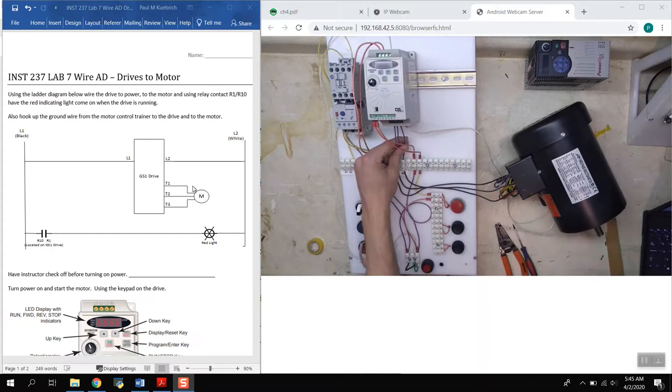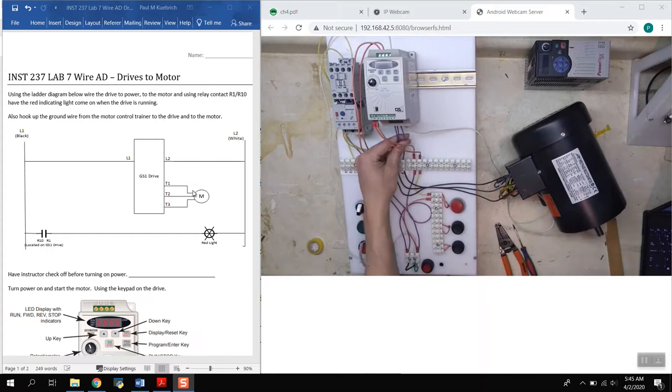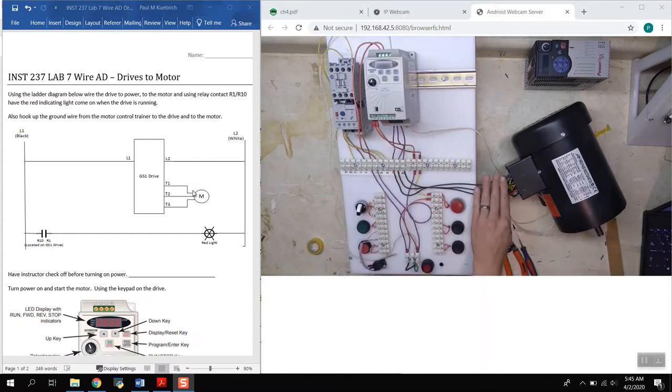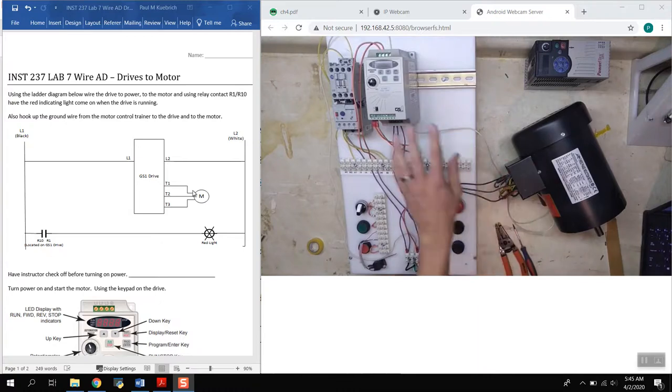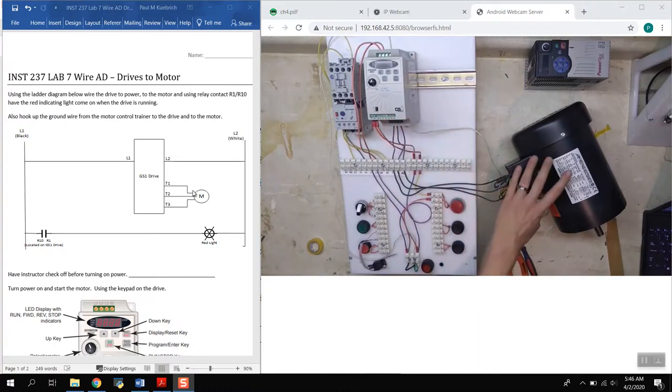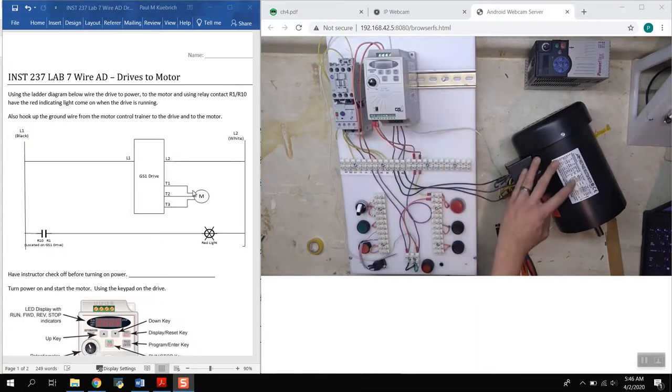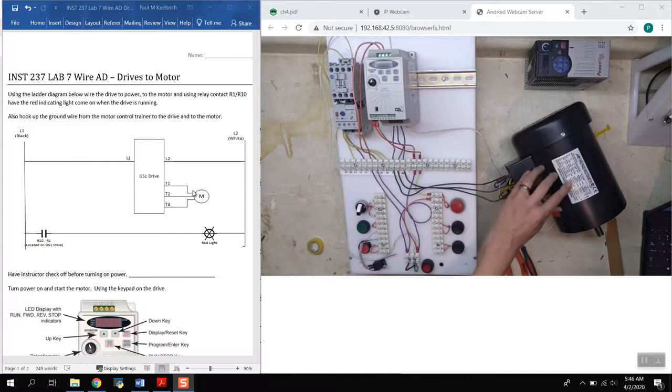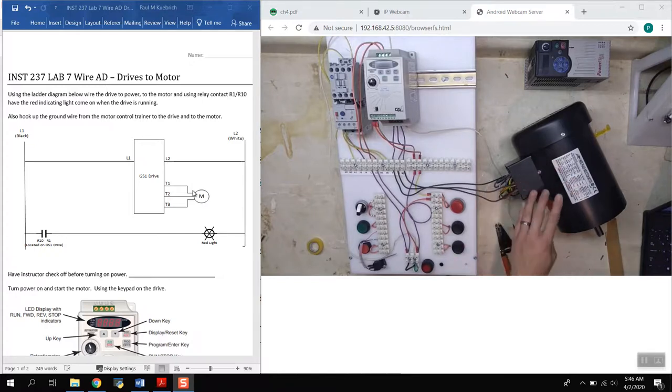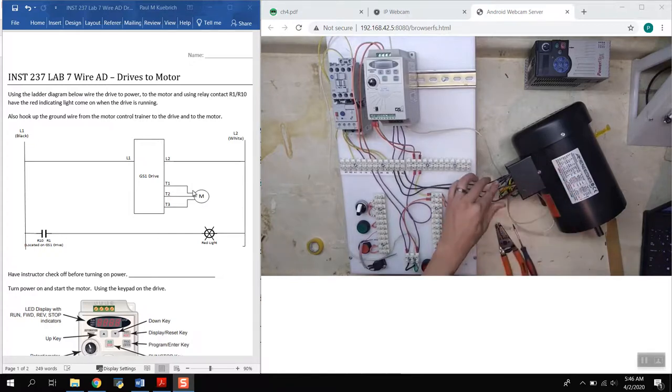Output of that drive then is T1, T2, and T3 which then go into the motor, shown here with these wires. This will convert it to 240 volts, so we are on the low voltage side of the motor. Make sure when you wire them up that you wire it up according to low voltage and not high voltage, not to 480.